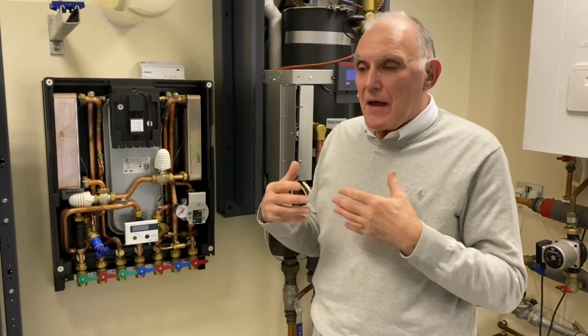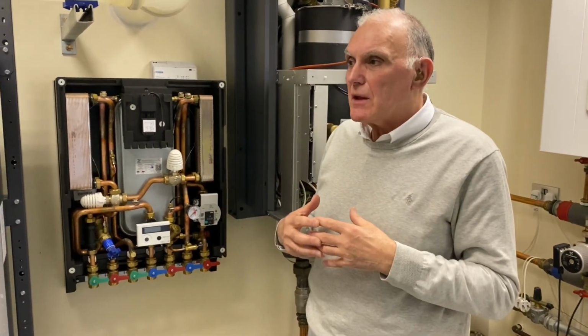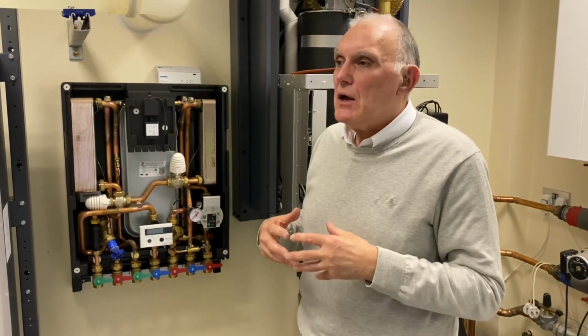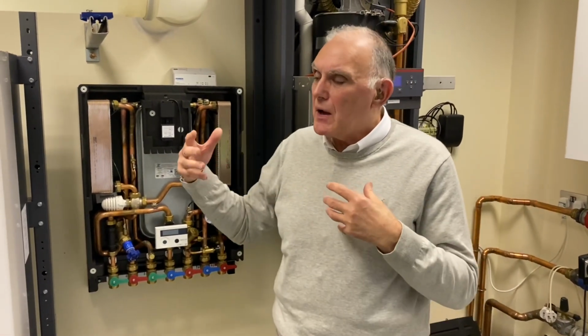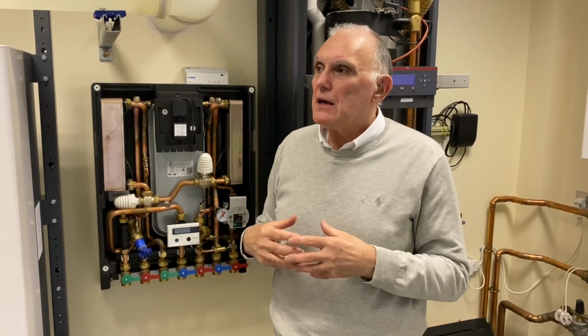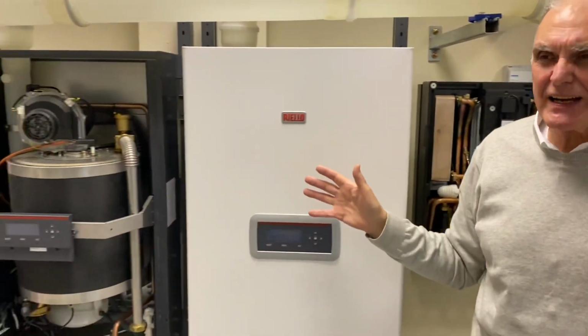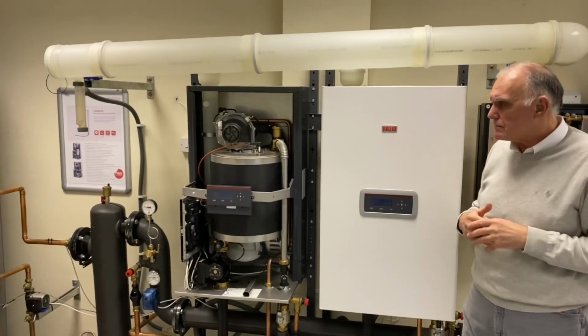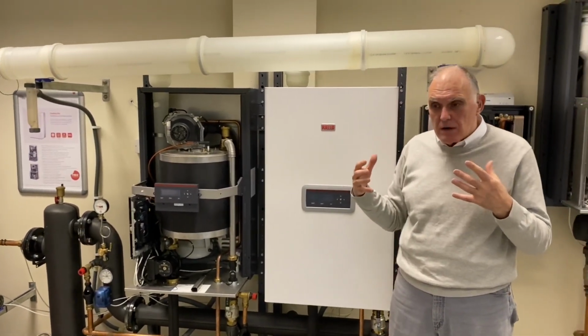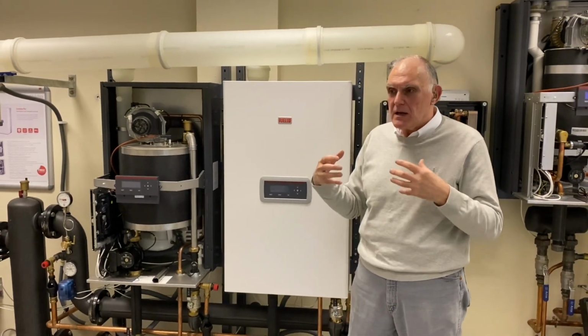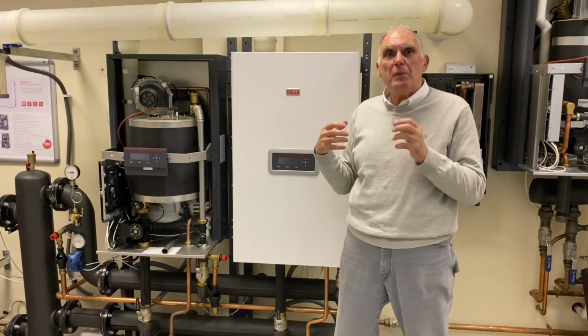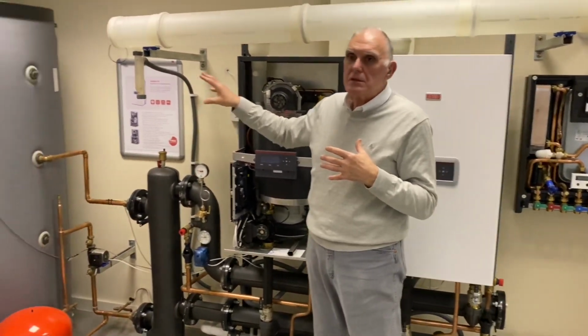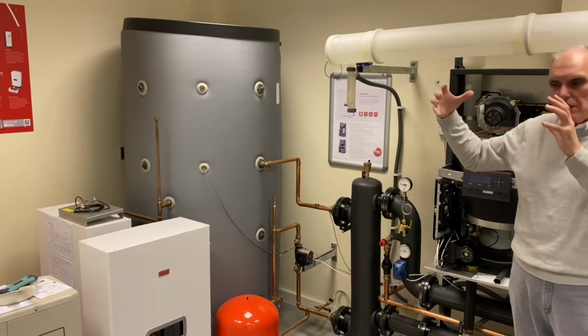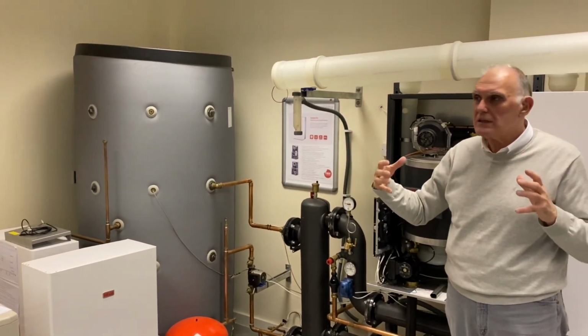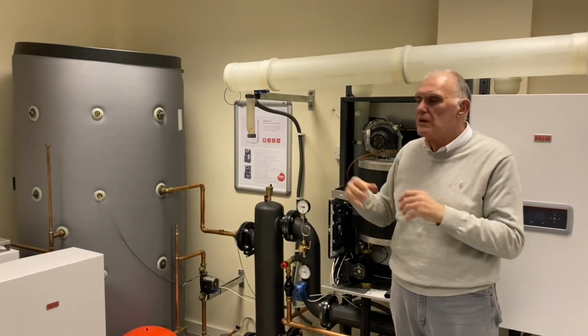And the other benefit is that we use these in some posh apartment blocks in the southwest of England. We would use this fed by perhaps a cascade of boilers. So there's backup on the boilers. If I can ask Charlie, our cameraman, just to show, this is one of our cascades. We can obviously have many boilers in our cascade. So what we've got is a cascade of boilers providing the main source of heat. If you can pan across, Charlie, we would use something like a thermal store. So that would be the thermal store of water, so the boilers don't operate continually. The heat energy is stored in a thermal store.